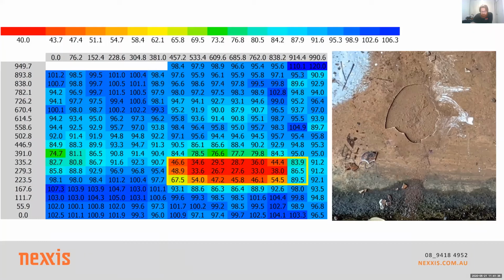Pulse eddy current tends to work in a reference capacity. When you get to an asset you're inspecting, you calibrate the probe to a nominal piece. You don't take a calibration piece with you like UT, you actually find nominal on the asset, or near nominal, that you can measure and adjust, and everything is referenced back to that. For this, we found some sort of nominal area up the top where there was likely not to be corrosion. We calibrated the system up there, and then started our inspection.